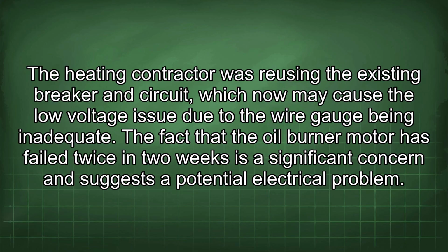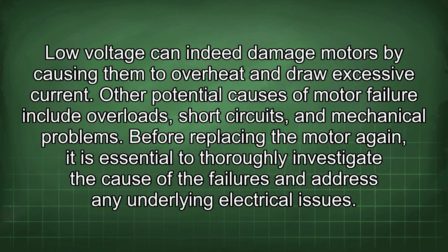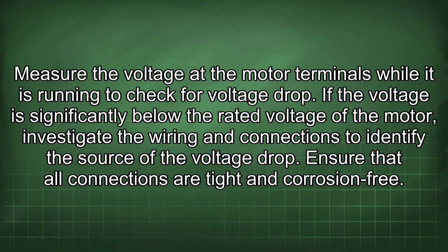The fact that the oil burner motor has failed twice in 2 weeks is a significant concern and suggests a potential electrical problem. Low voltage can indeed damage motors by causing them to overheat and draw excessive current. Other potential causes of motor failure include overloads, short circuits, and mechanical problems. Before replacing the motor again, it is essential to thoroughly investigate the cause of the failures and address any underlying electrical issues. Measure the voltage at the motor terminals while it is running to check for voltage drop. If the voltage is significantly below the rated voltage of the motor, investigate the wiring and connections to identify the source of the voltage drop.